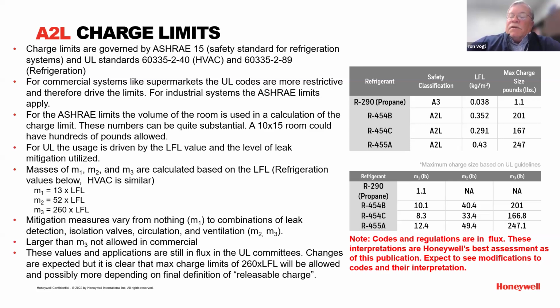So it's a little complicated, but I want to point out that these refrigerants are different. Looking at the chart on the top right, propane - we talked about it - the max charge here, and this is an update, with LFL, is 1.1 pounds. I'm not sure where that would even be applied, but you can see the difference versus 454, 454C, and 455 - anywhere from 200 up to 250 pounds you could use based on the LFL.